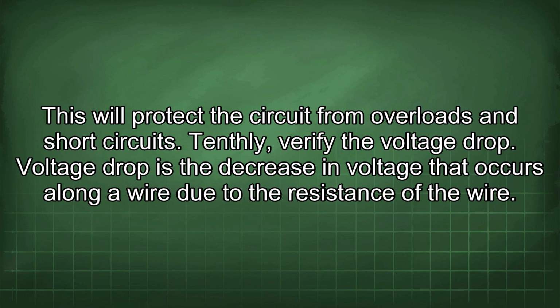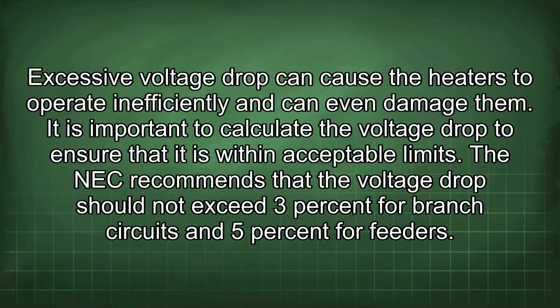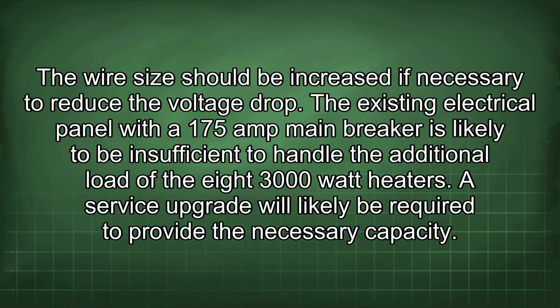Tenthly, verify the voltage drop. Voltage drop is the decrease in voltage that occurs along a wire due to the resistance of the wire. Excessive voltage drop can cause the heaters to operate inefficiently and can even damage them. It is important to calculate the voltage drop to ensure that it is within acceptable limits. The NEC recommends that the voltage drop should not exceed 3% for branch circuits and 5% for feeders. The wire size should be increased if necessary to reduce the voltage drop.